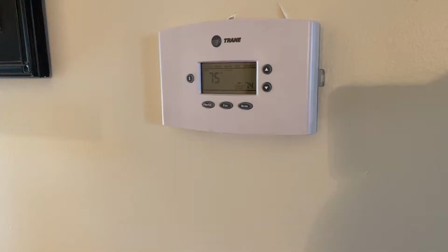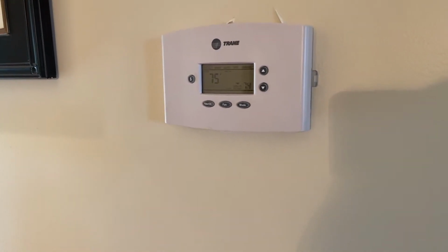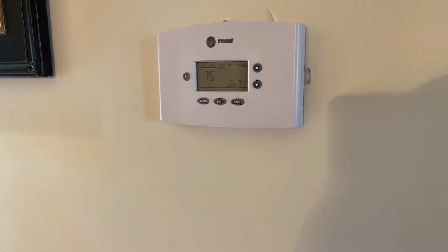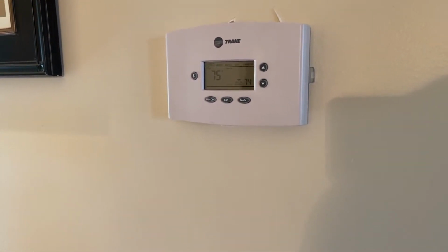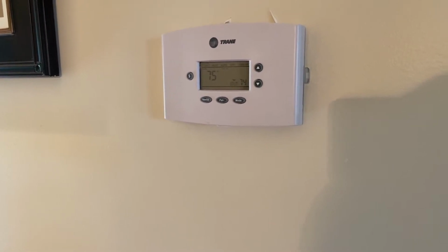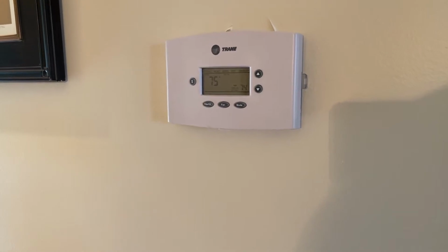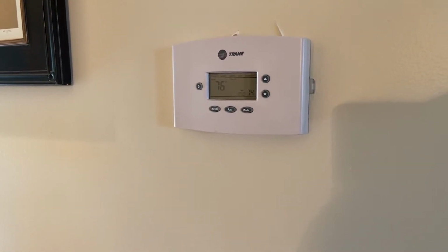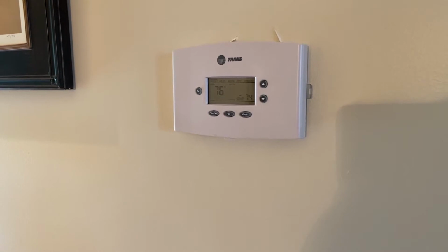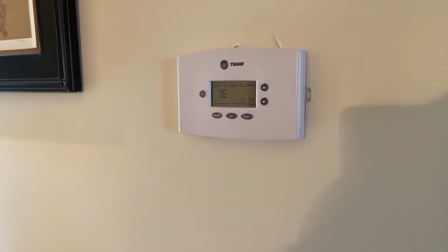So it was hot in the house today, and I want to show you what is usually the problem if your air conditioner stops unexpectedly. So the first thing to look at is the thermostat. If the screen is blank, chances are it's because your condensate line is clogged. That's that little pipe that comes out the side of your house that drips water. Well, if that gets clogged, then the air conditioner is going to stop automatically, or at least it's supposed to, before it makes a mess. So I'll show you what I mean.